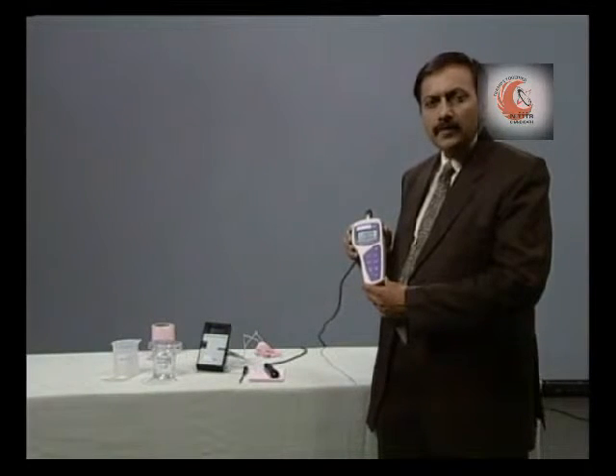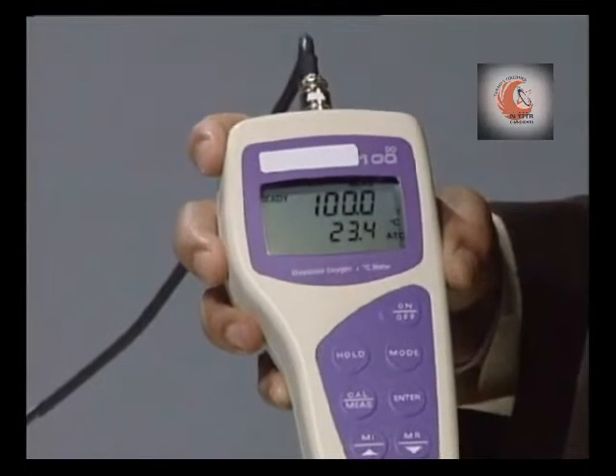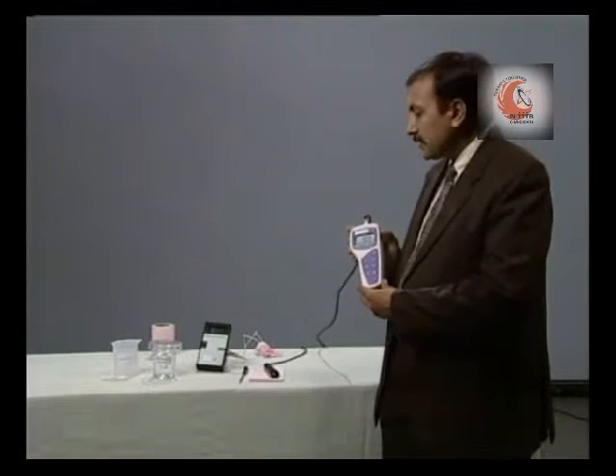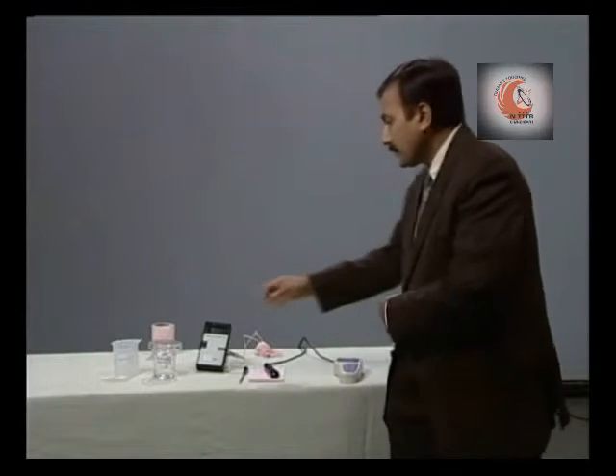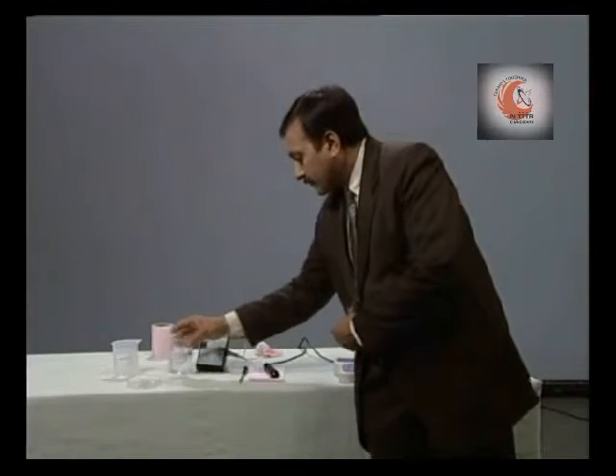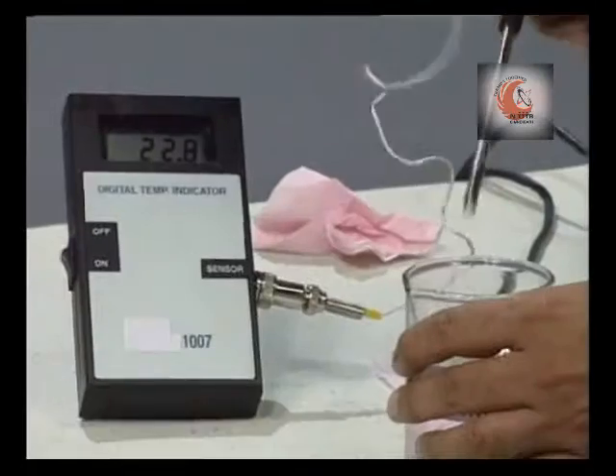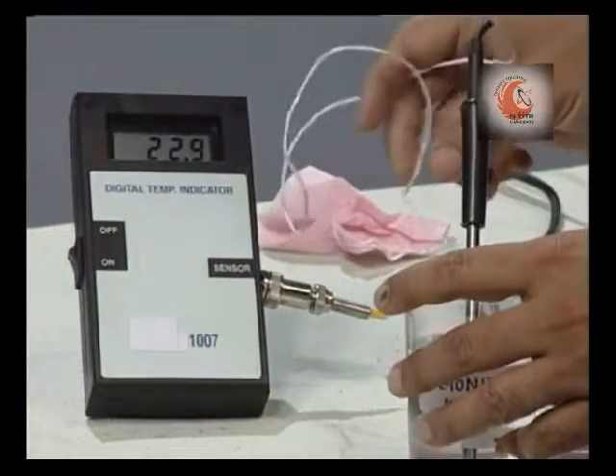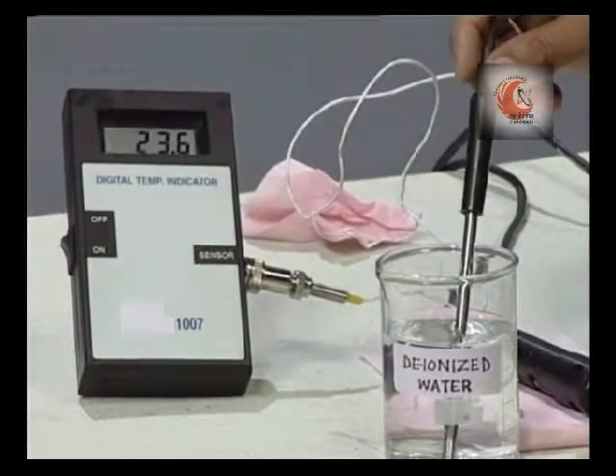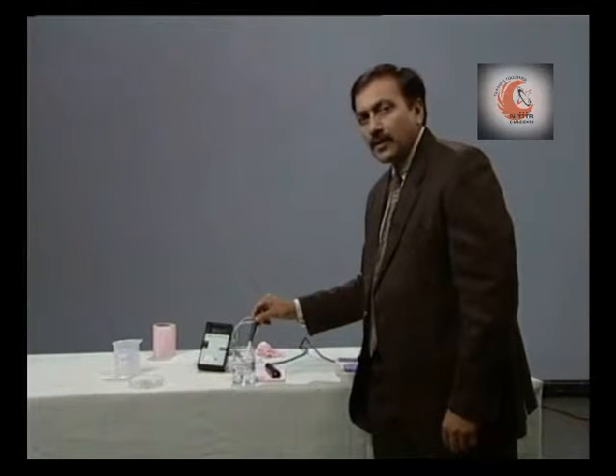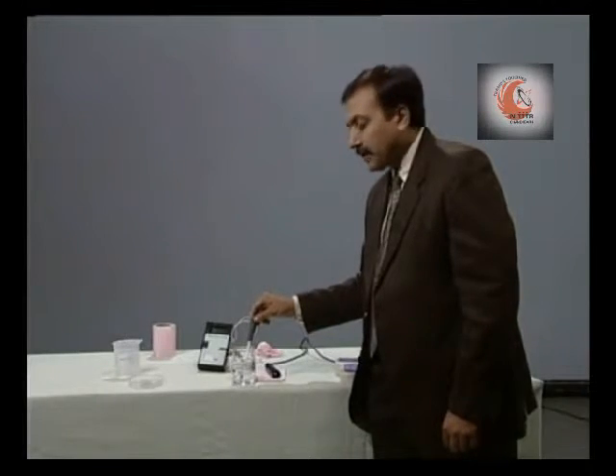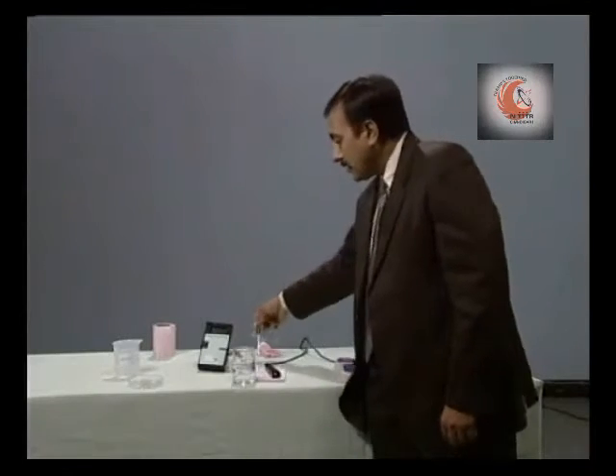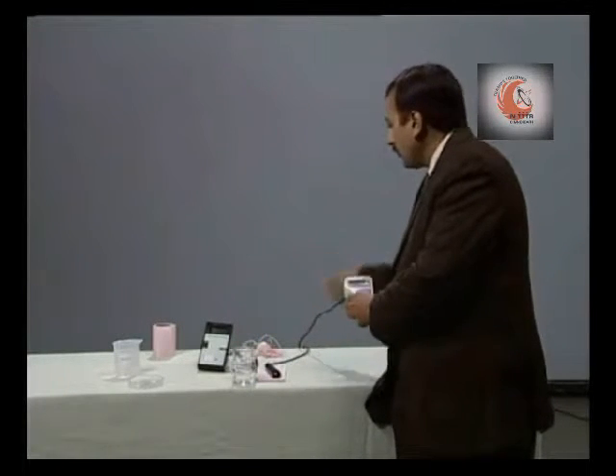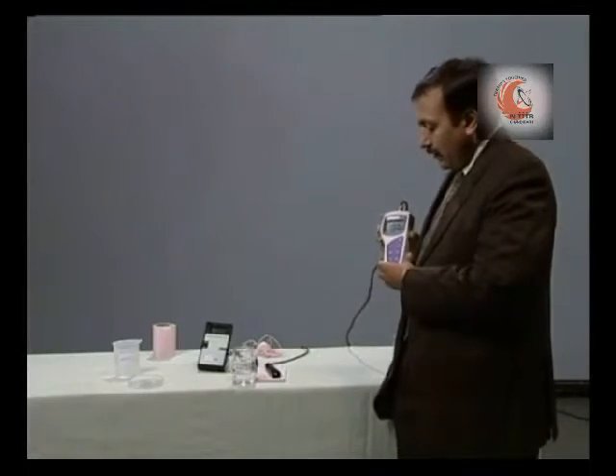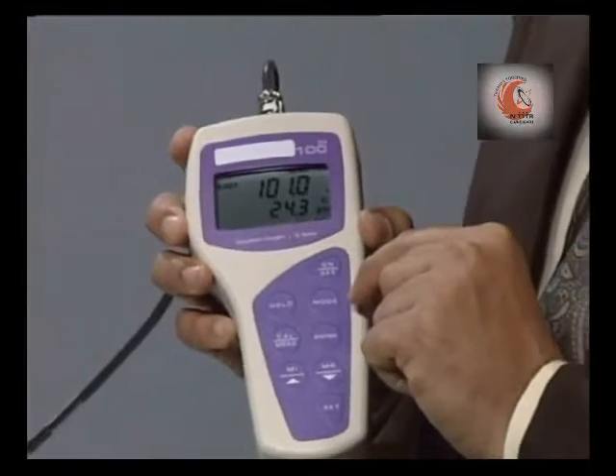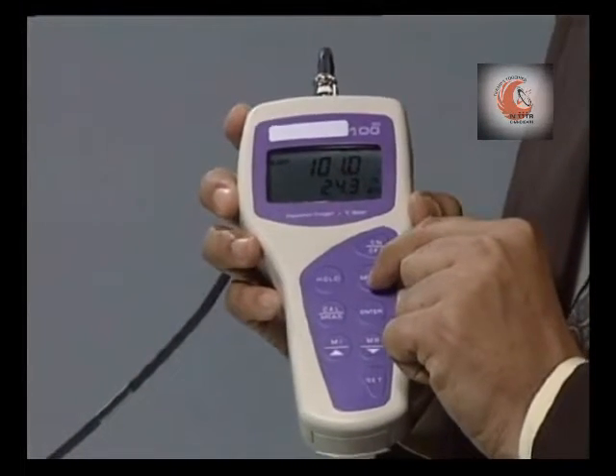The second correction is for temperature. To do this, we shall first measure the temperature of the solution. The temperature of the solution is 23.6 degree centigrade. Now the same value has to be adjusted on the instrument. So first we put the instrument in temperature mode. Now press mode.